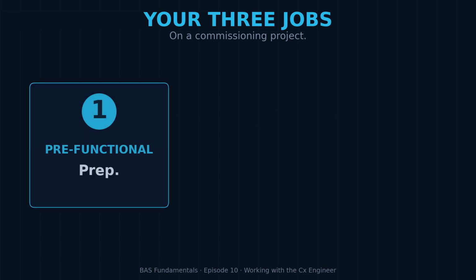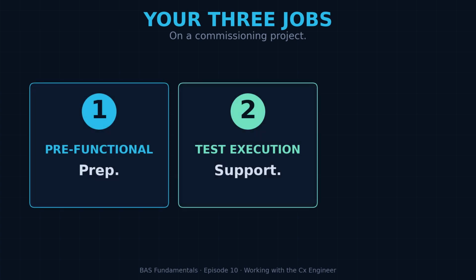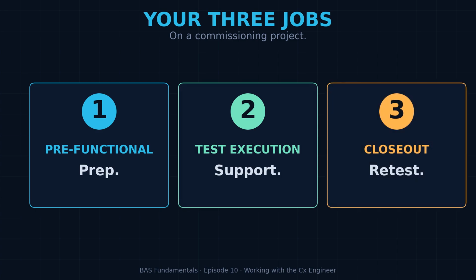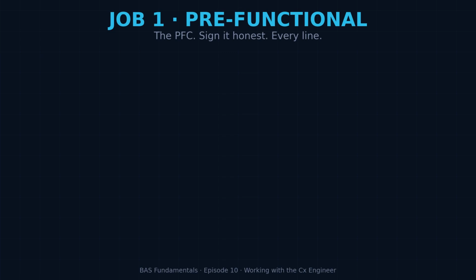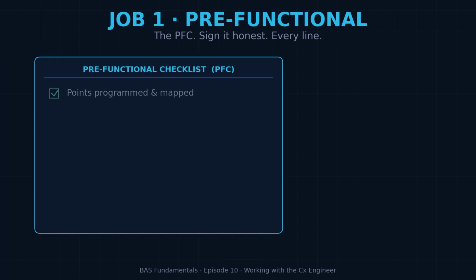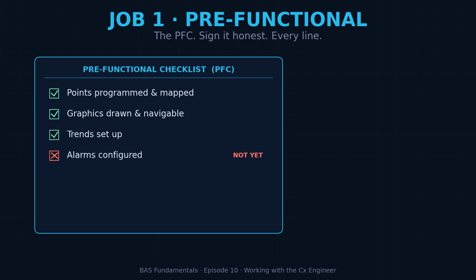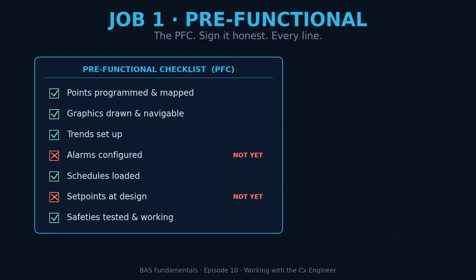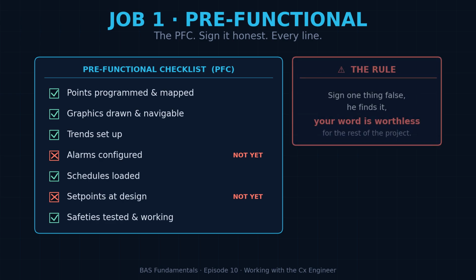Your 3 jobs on a commissioning project. 1. Pre-functional preparation. 2. Test execution support. 3. Deficiency closeout. Let's take pre-functional first. Before the agent runs a single test, he is going to send you a pre-functional checklist, sometimes called the PFC. It's a list of everything that has to be true before functional testing can even start. Points programmed and mapped. Graphics drawn and navigable. Trends set up. Alarms configured. Schedules loaded. Set points at design. Safeties working. All of it.